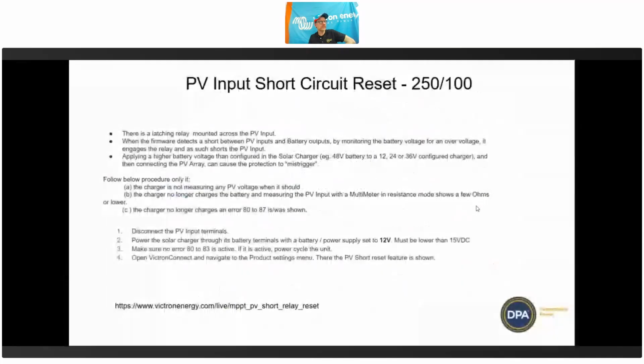And so finally, some tips and tricks. This is what I was talking about before, the input short circuit reset. Basically, if the MPPT—and this is mainly in the larger models, although I think they're starting to roll this out with the smaller ones as well—if it sees the battery voltage as being way higher than it thinks it should be, then it will short out the PV input terminals so that it doesn't cook the batteries.